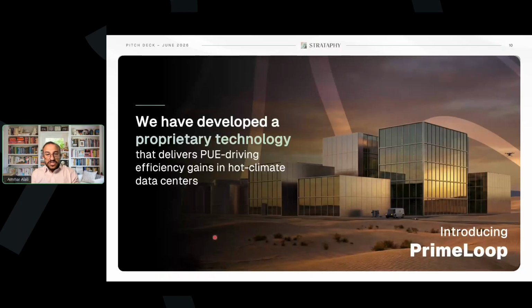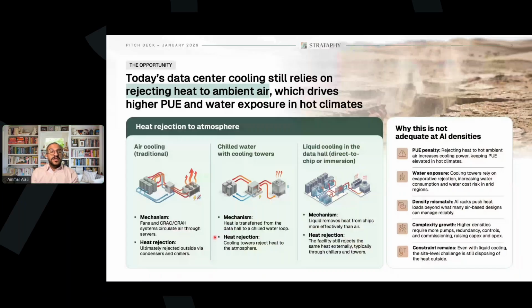All of these solutions, in my opinion, are not ideal, because they tend to be extremely reliant on what the temperature and condition outside are. So if the temperature outside is 35 degrees Celsius, you're going to get a different efficiency than if it is 45 or 55 degrees, especially in the Middle East, versus if it's 20 degrees. So you're always vulnerable to the conditions outside: the humidity, especially for cooling towers, the temperature for air cooling, and so on and so forth.